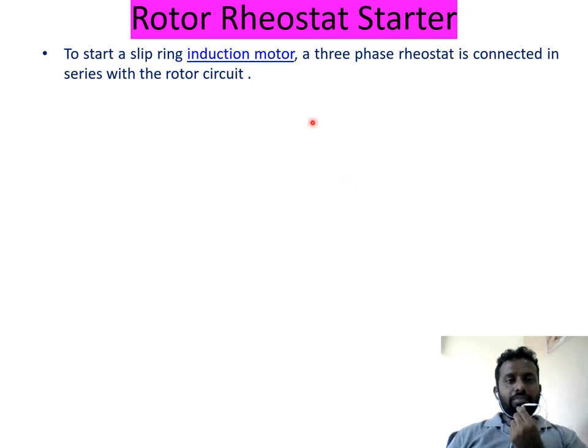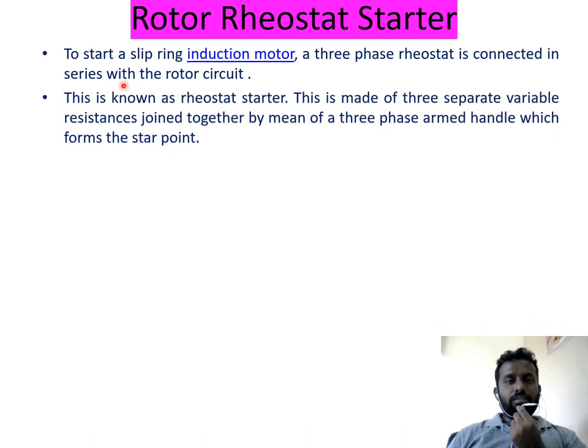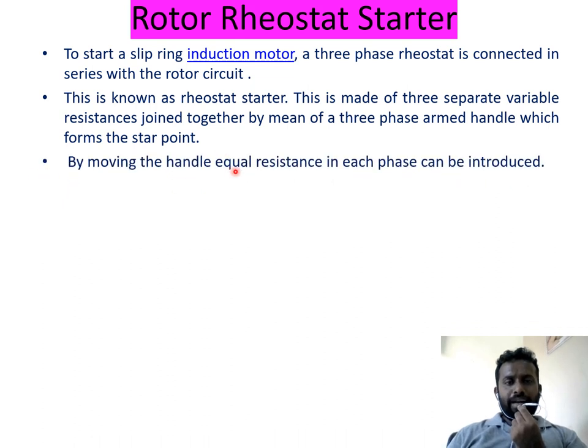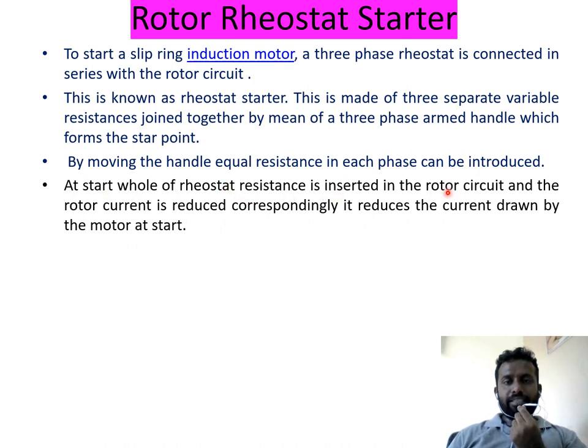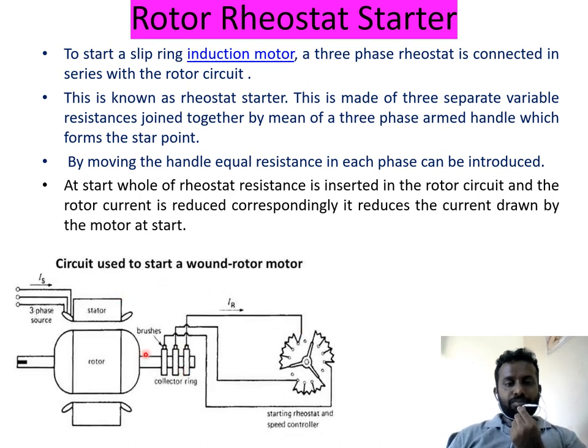Rotor Rheostat Starter: to start a slip ring induction motor, a three-phase rheostat — a variable resistor — is connected in series with the rotor circuit. This is known as the rheostat starter. It is made of three separate variable resistors joined by a three-phase armed handle which forms the star point. By moving the handle, equal resistance in each phase can be introduced. At start, the full rheostat resistance is inserted in the rotor circuit, reducing the rotor current and the current drawn by the motor at starting.